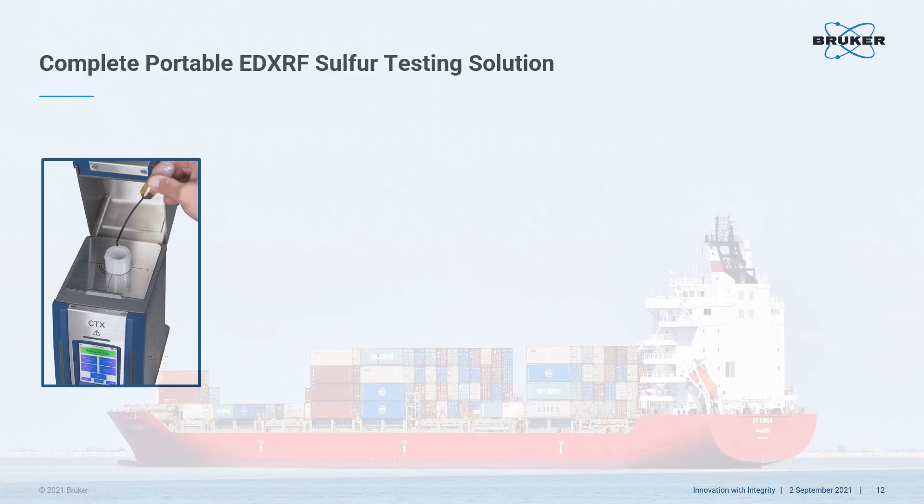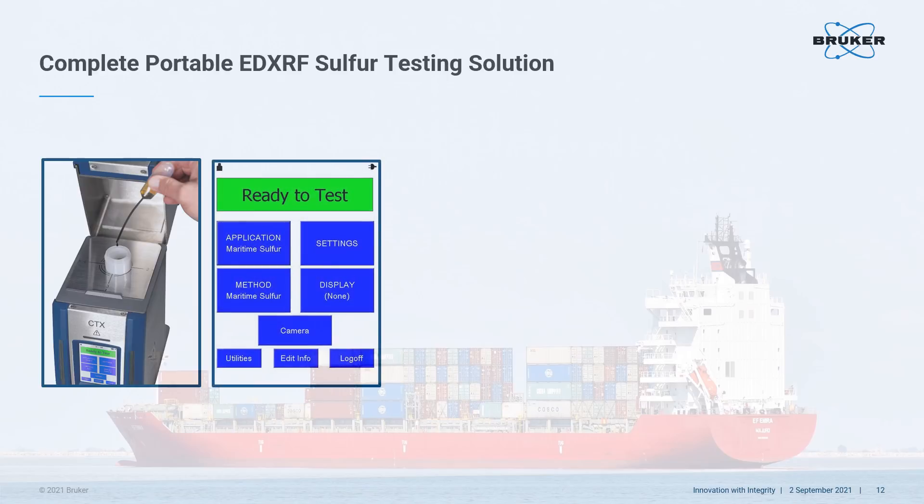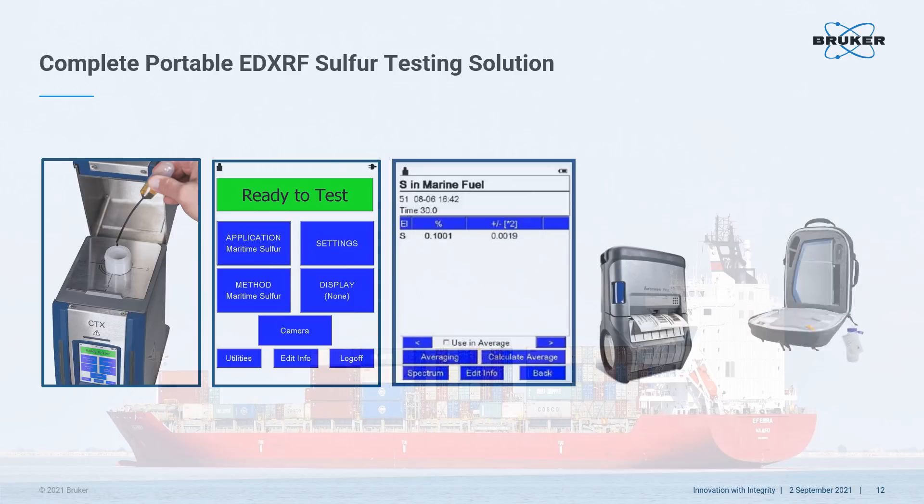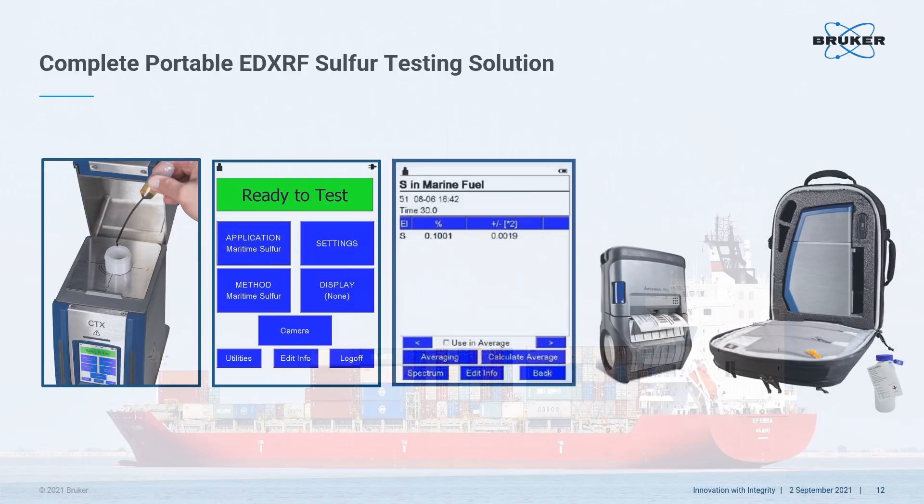In summary, if you need to measure sulfur in fuel for MARPOL's Annex 6 Regulation 14, following an authorized method such as ASTM D4294-16e1, a portable EDXRF analyzer with a maritime sulfur calibration installed will provide accurate and precise answers in as little as one minute or less. Results can be saved on the analyzer or transferred to a printer, USB stick, or PC. All of the materials along with the analyzer can be secured in a backpack for convenient analysis at service labs, supply stations, on docks, in ports, and even aboard barges and ships.